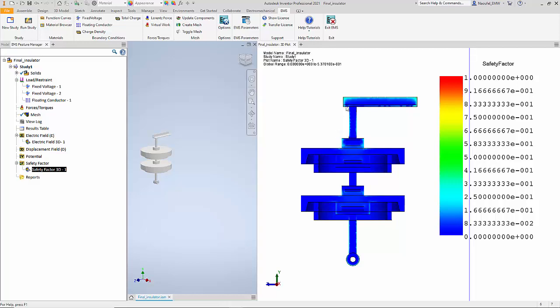As we see, most of the regions or almost all the regions in the insulator are in the bottommost blue. So we can be very sure that the insulator design ensures no breakdown when it is connected to an 80 kilovolt voltage source.